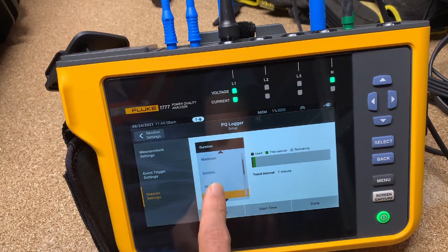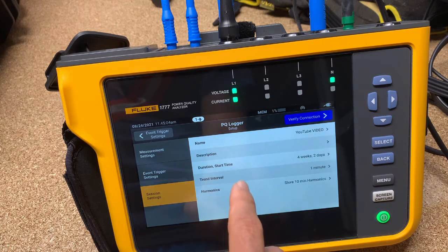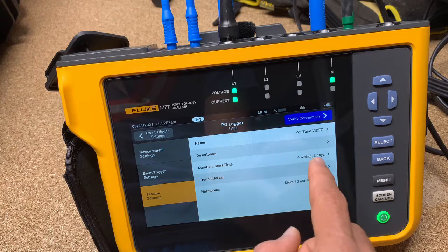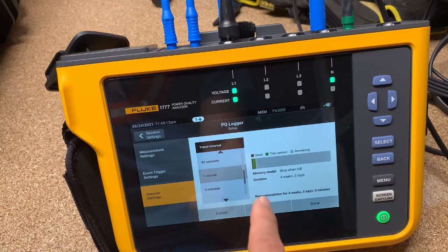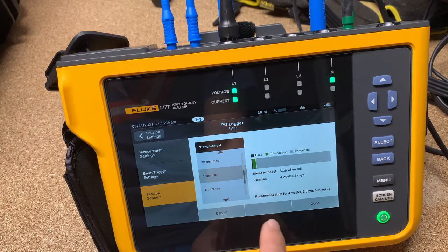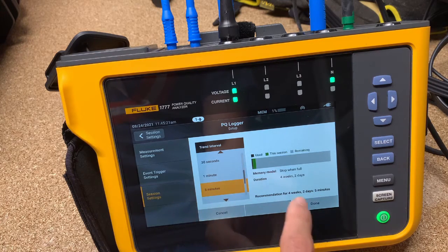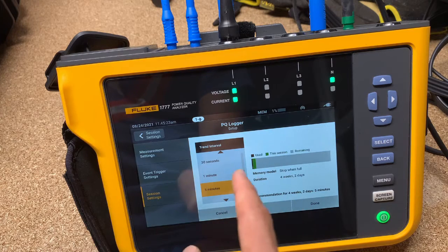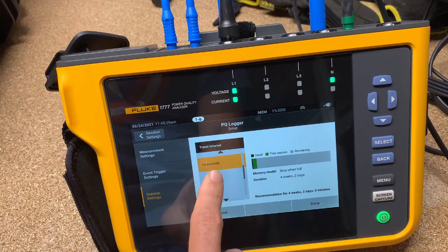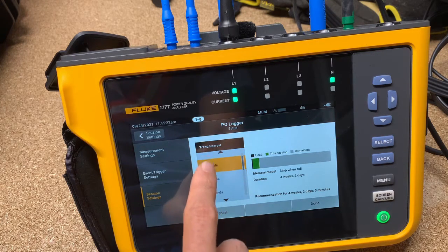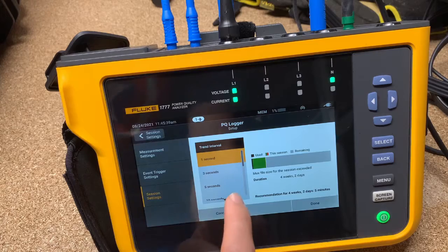Let's say we want to do a 30-day study. So 30 days, and then time interval — this is going to be your averaging interval. You can see recommended for four weeks is five minutes. The five minutes is what's recommended, which will actually make the memory less or more depending on what you do. A lot of people think bigger files are better, but that's not necessarily the case.